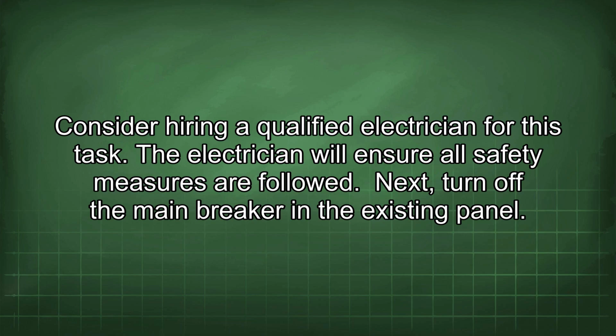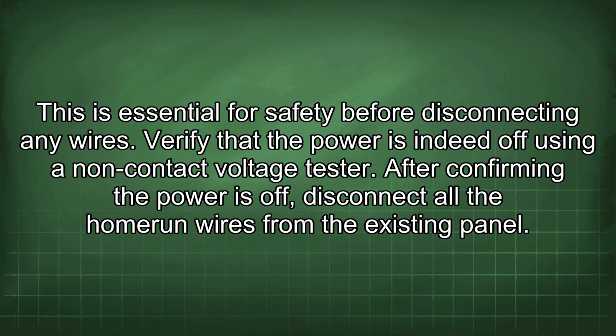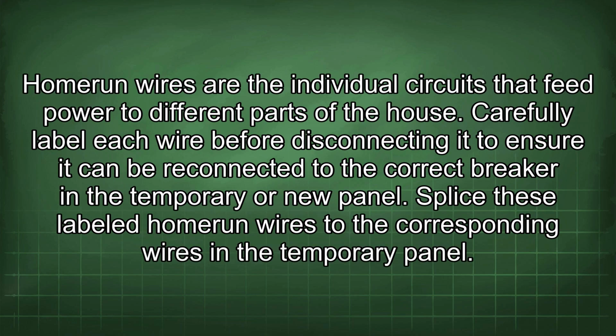Next, turn off the main breaker in the existing panel. This is essential for safety before disconnecting any wires. Verify that the power is indeed off using a non-contact voltage tester. After confirming the power is off, disconnect all the homerun wires from the existing panel. Homerun wires are the individual circuits that feed power to different parts of the house.